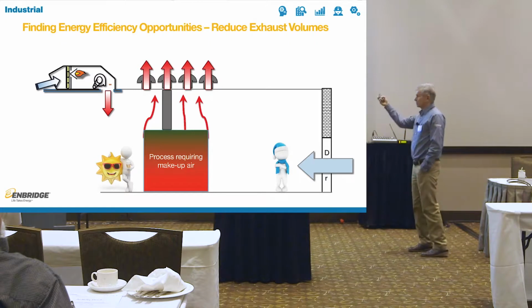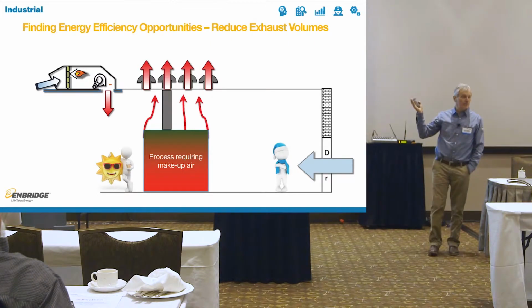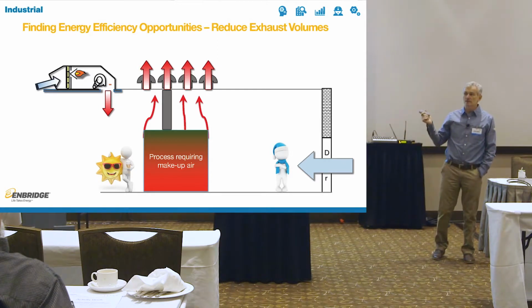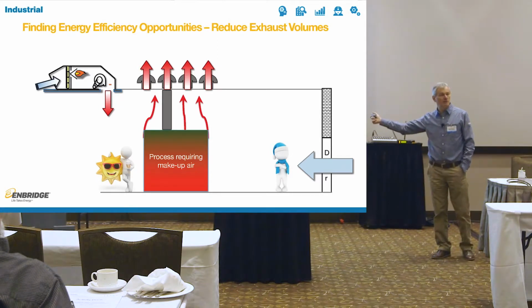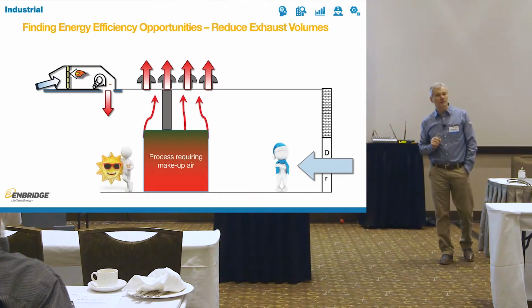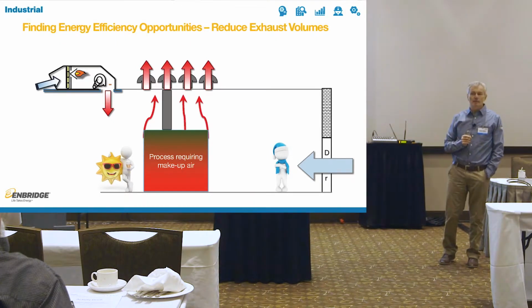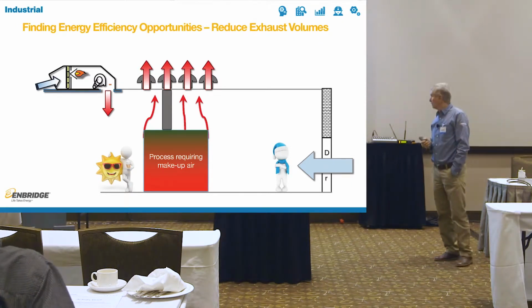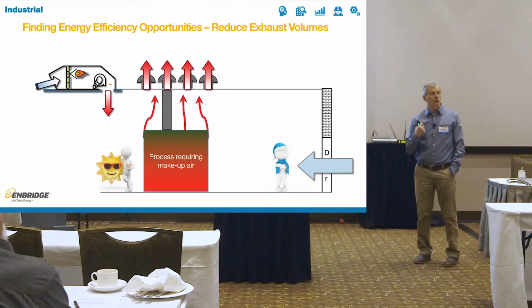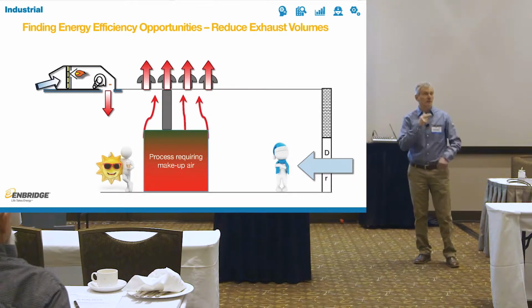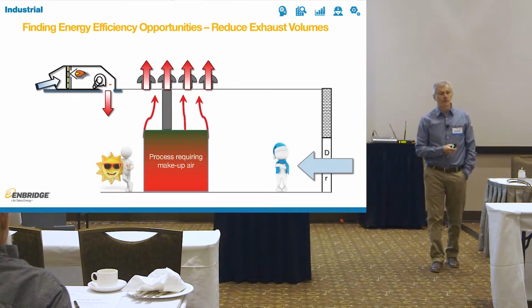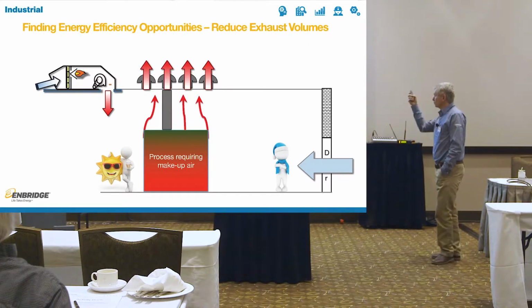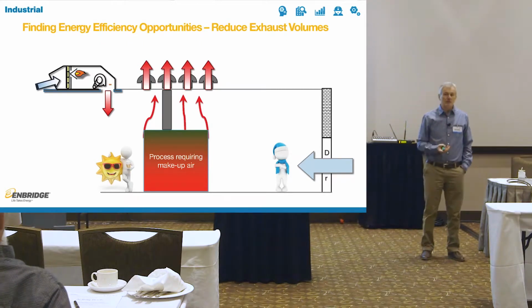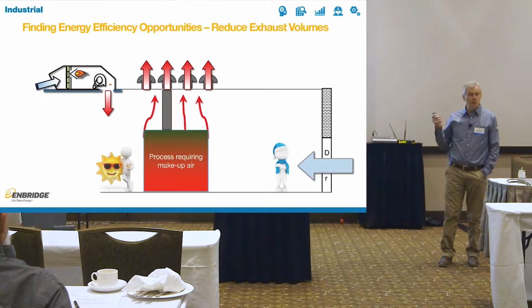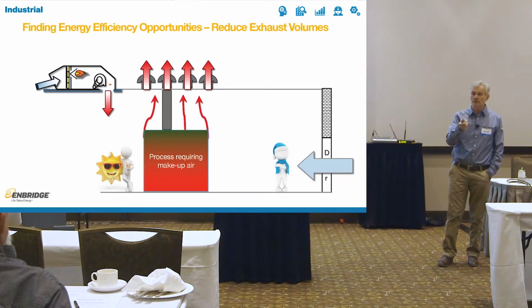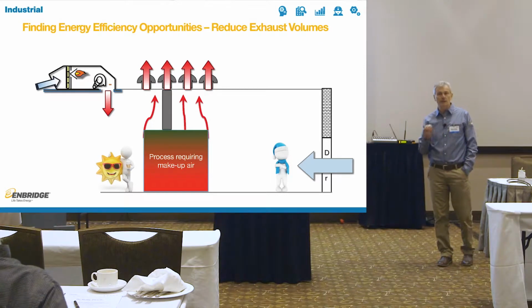But there are also some shell losses, so it gets warm around it. So comes July, August, people around the facility start to complain, especially the guy who has to sit right next to it because he's monitoring the little panel there and making sure that widgets go in and out correctly. Now he gets a little warm. You give him a water bottle, that's not good enough. He wants to walk off the facility. He says, it's 38 degrees Celsius in here, I'm off. What does your plant manager do? Oh, damn it, just put in more exhaust. Get rid of the heat. The more, the better. And it is the right solution for the summer. Absolutely, you have to get rid of that.